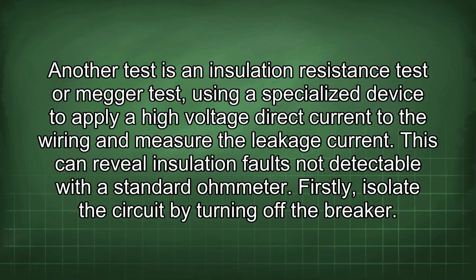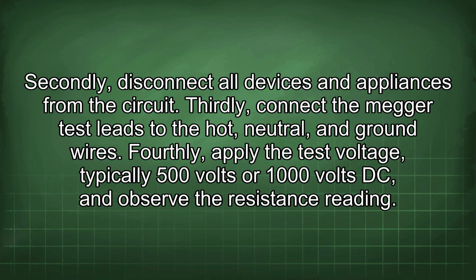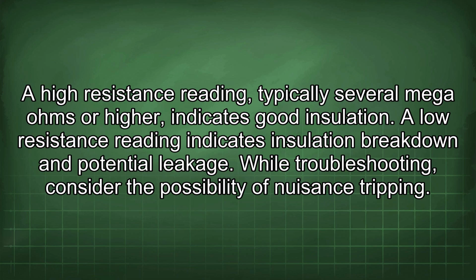Firstly, isolate the circuit by turning off the breaker. Secondly, disconnect all devices and appliances from the circuit. Thirdly, connect the megger leads to the hot, neutral, and ground wires. Fourthly, apply the test voltage, typically 500 volts or 1000 volts DC, and observe the resistance reading. A high resistance reading, typically several megaohms or higher, indicates good insulation. A low resistance reading indicates insulation breakdown and potential leakage.